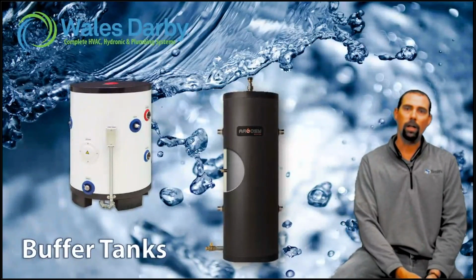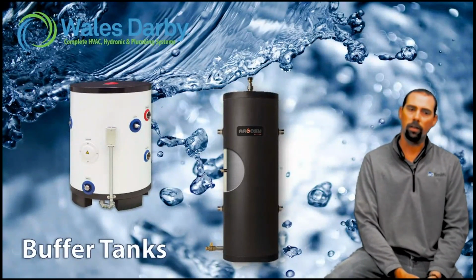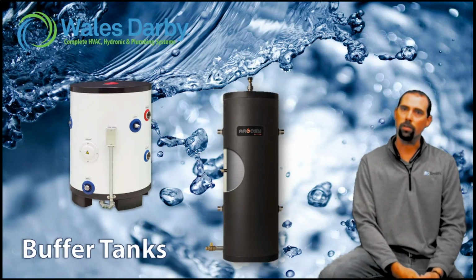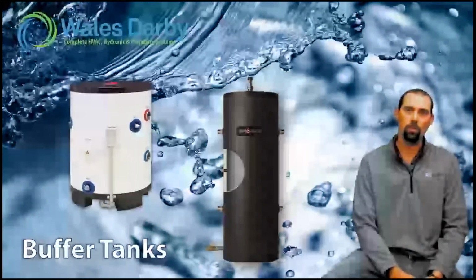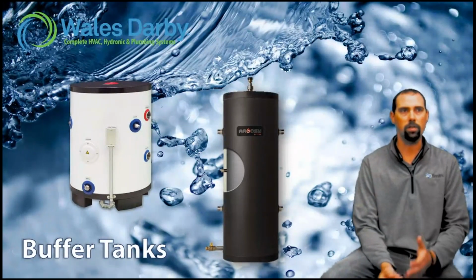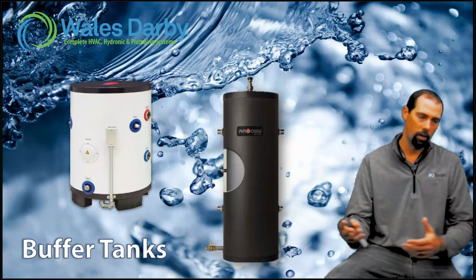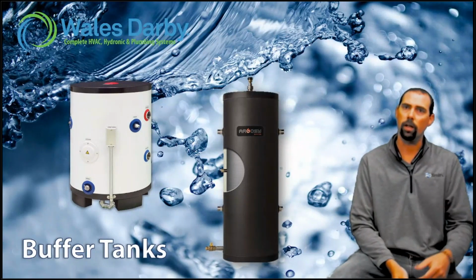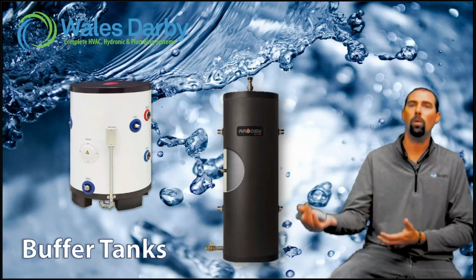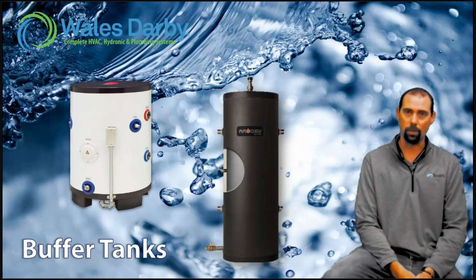Moving on to the next component in that system, the buffer tanks. They're BTU batteries, really all they are. They're hydraulic separators, giving us two different flows, from our outdoor unit and then our indoor. So it's a decoupler of the hydronic system.